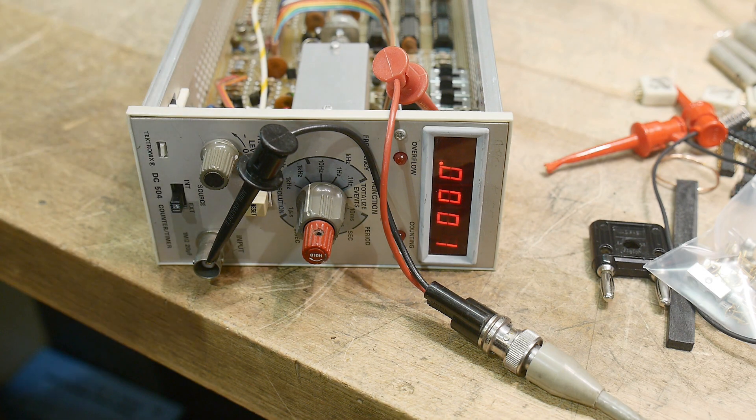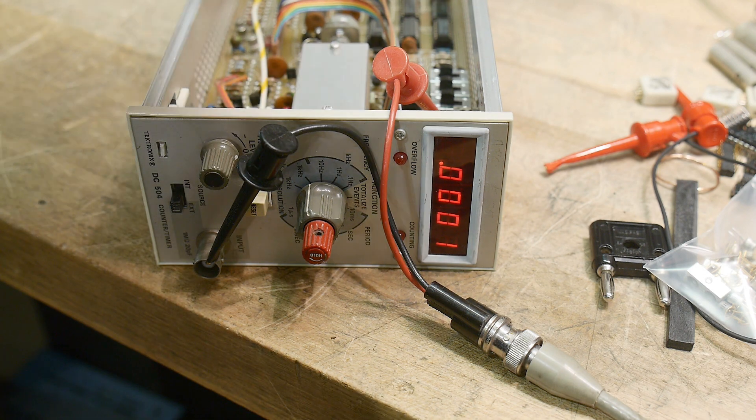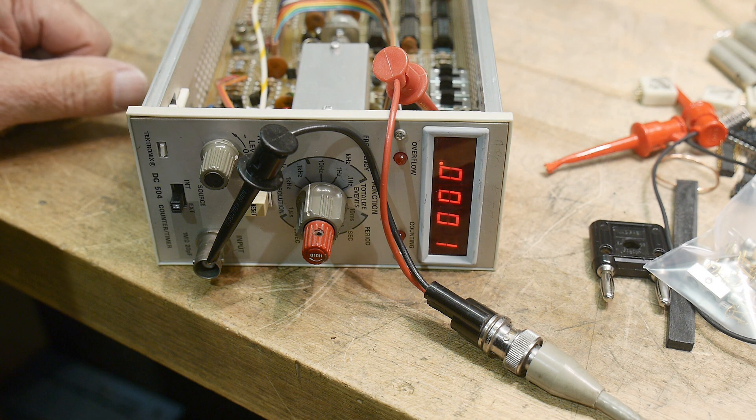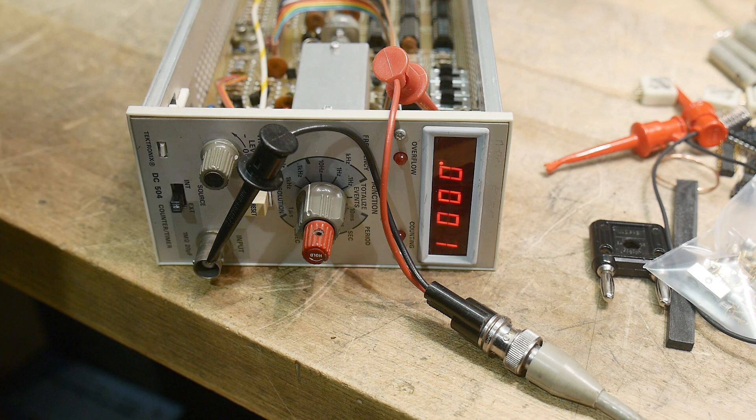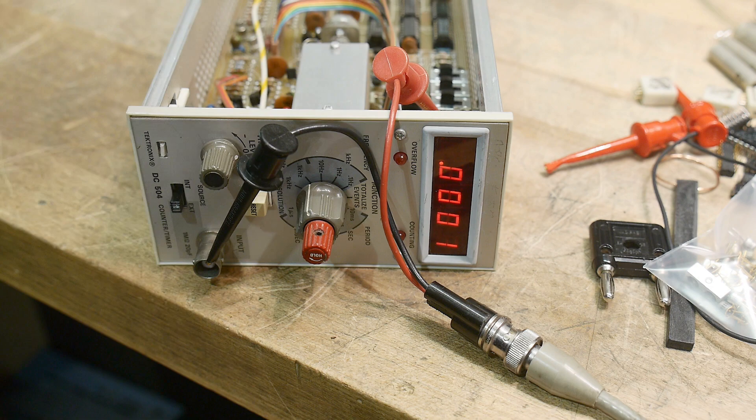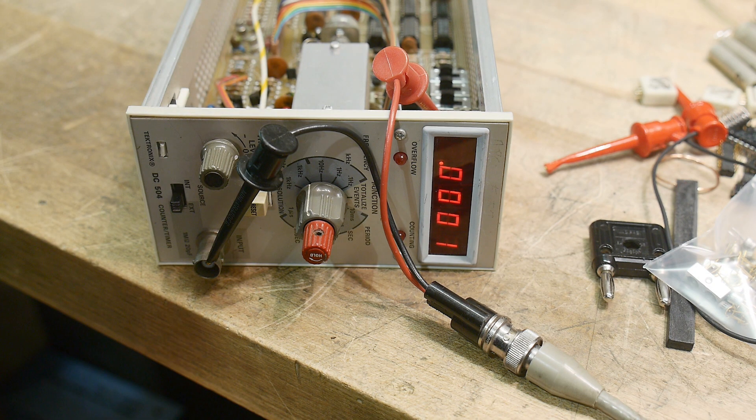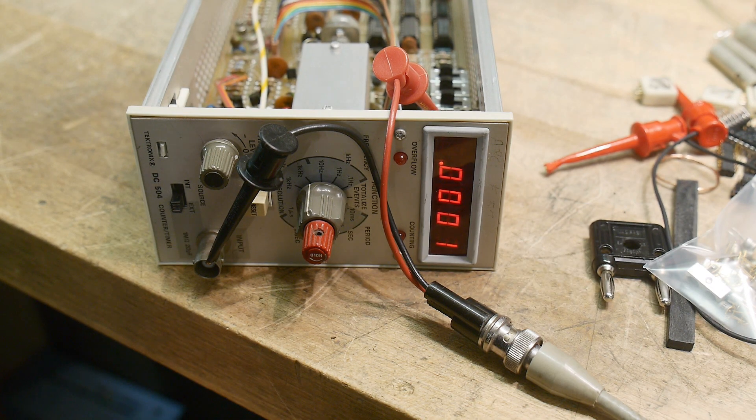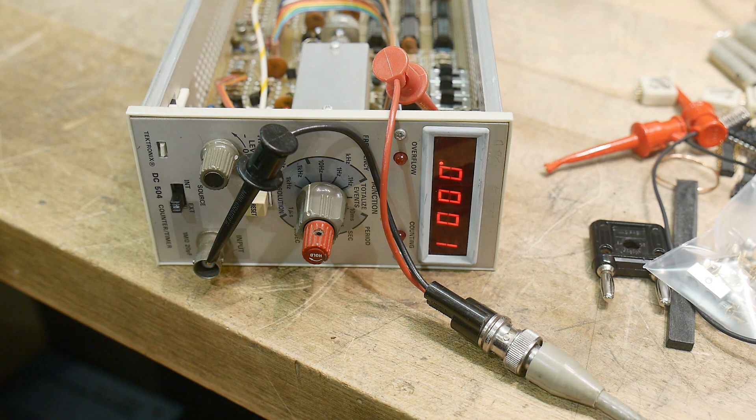The first thing I'm going to do before checking it out is to adjust the internal oscillator, which is pretty crude. It's just a one megahertz crystal, one of those really big ones, and a capacitor that you fiddle with to make it one megahertz. And then it counts from there. So probably not the most accurate time base, but that's the way this thing is designed.